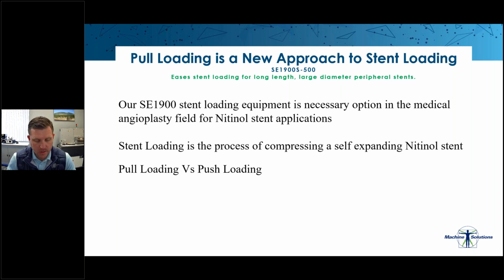So now we're going to go into greater detail about pull loading versus push loading. When we talk about pull loading with our new SE 1900S-500 machine, this machine is going to be used for large diameter peripheral stents up to 230 millimeters in length and up to 50 millimeters of non-compressed diameter, and is mainly used for angioplasty procedures. Using our patented segmental stent crimping compression head, the stent is compressed to the desired delivery diameter.